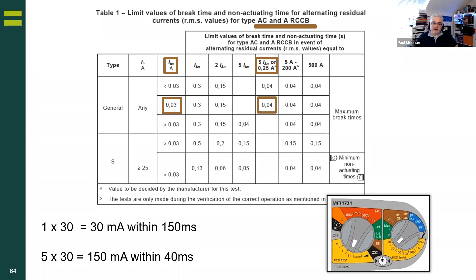Anyway, so let's look at table 1 very simply. There are 2 tables, table 1 and 2. For type AC and A, it shows you your I delta N of 0.03, which is obviously your 30 milliamps. And then you've got 5 times I delta N or 0.25 of an amp. Now that's the only reference to that 0.25, and in our language, it's 250 milliamp. This caused a lot of controversy on social media. How do I do it? Do I set my tester to 500 milliamp and half? Where's this all come from? Well, it came from table 1, and it was in the last amendment to the standard. So it has caused a lot of controversy, but this is the one that we need to be looking at now, and this is the reasoning behind it.